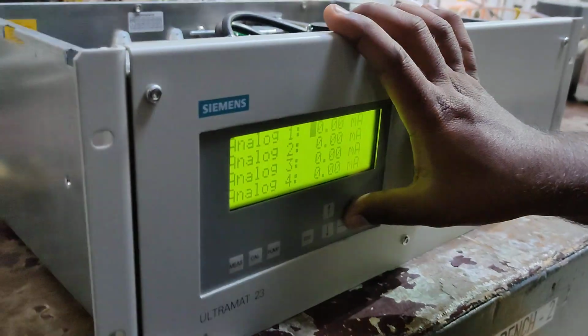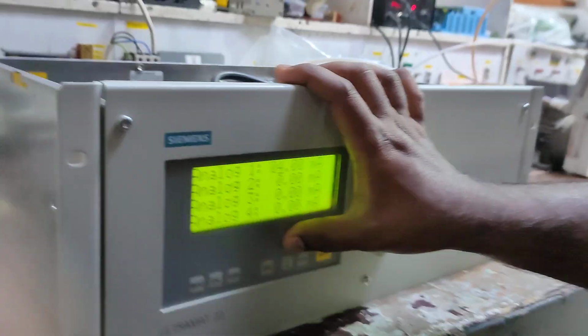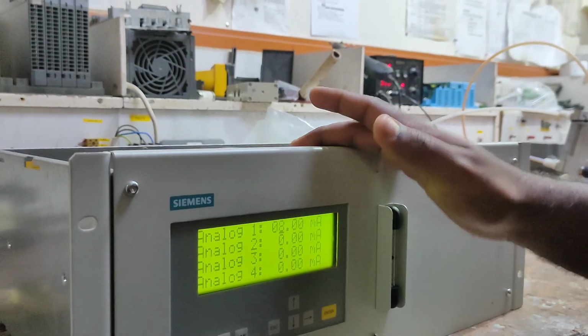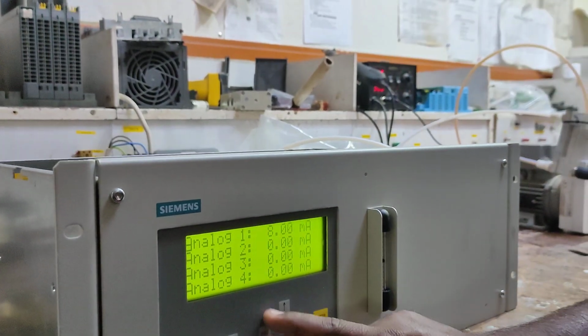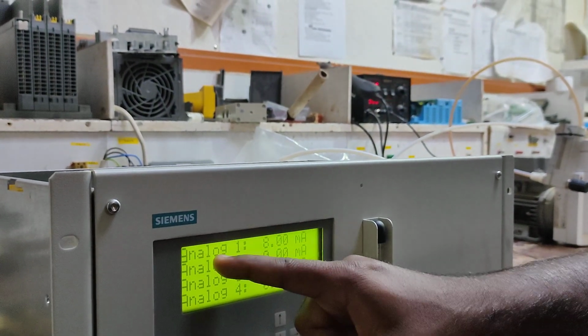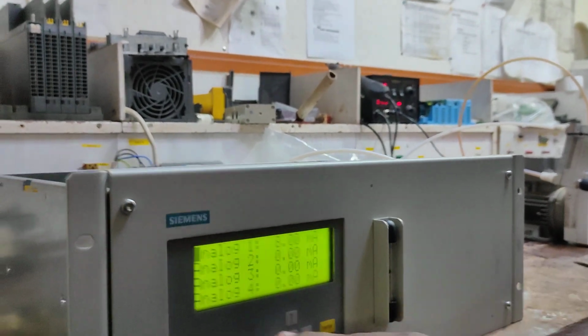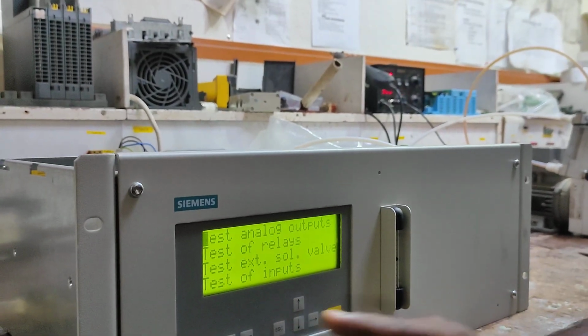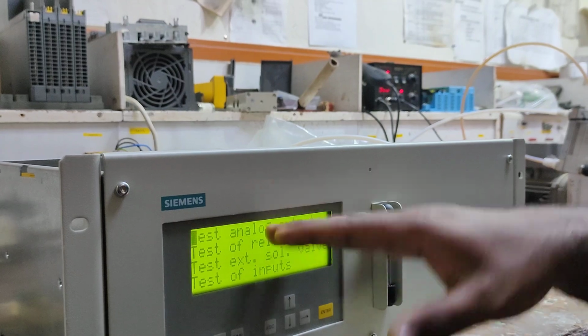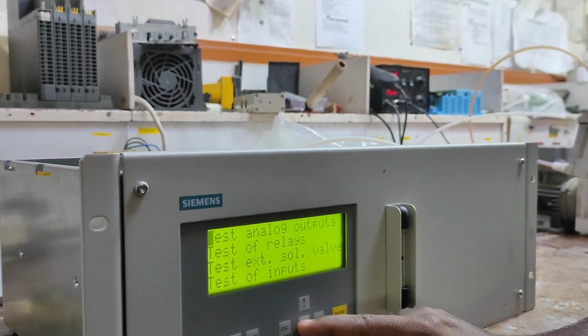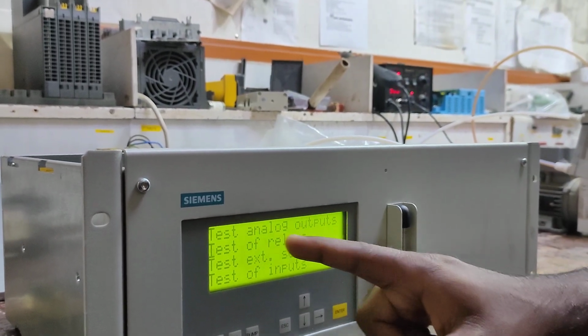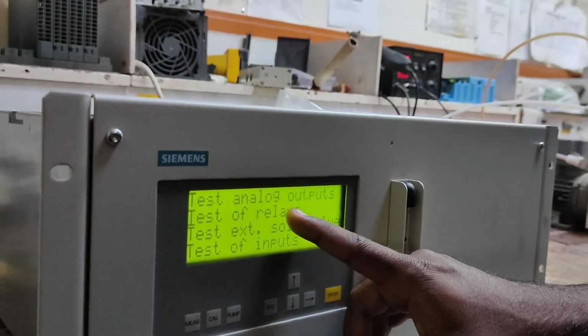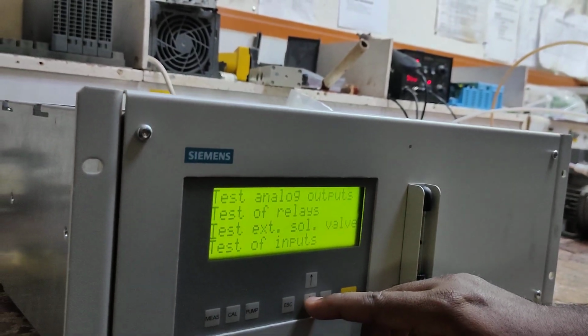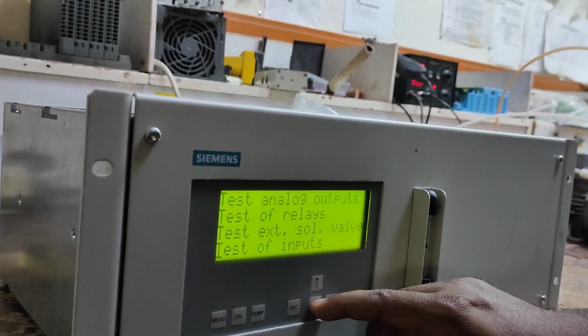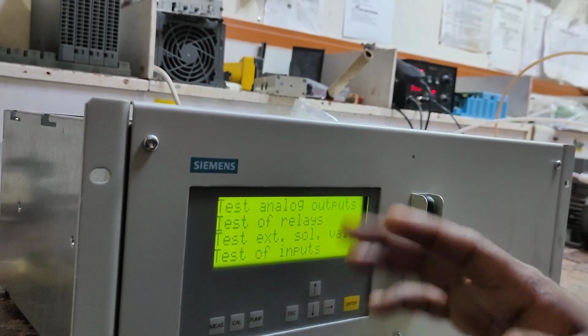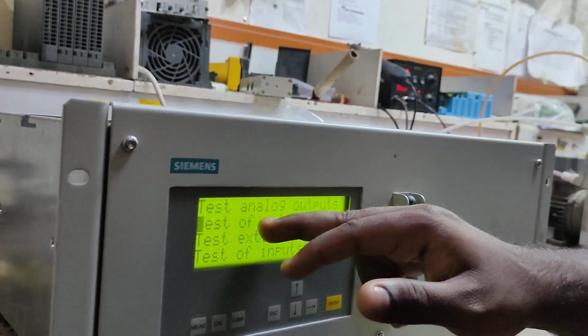Here you give the milliampere. We can measure the output. Output is 50% coming, and the analog output should come. Similarly, for you, 2 and 3 are not connected, only 1 and 4. Once you simulate, the simulated value will be output, and then it will go back to the actual. Similarly, you can test the relay also, and the DOs. Then you can select the external solenoid valve. We are not connecting it, so for this we need these two.